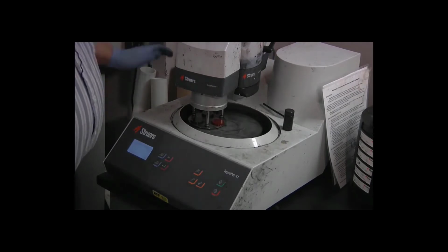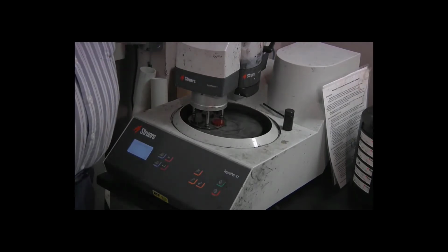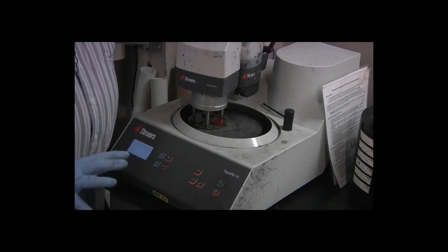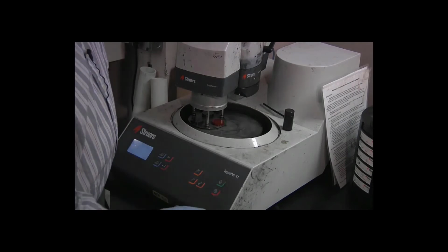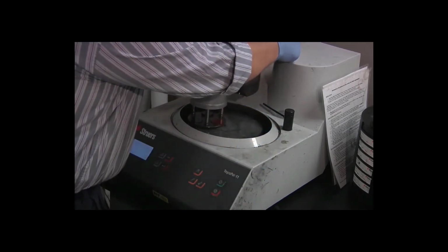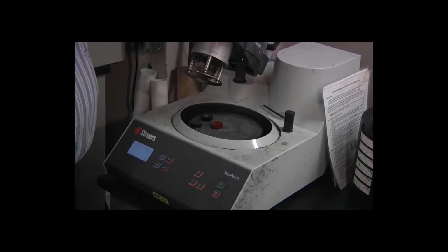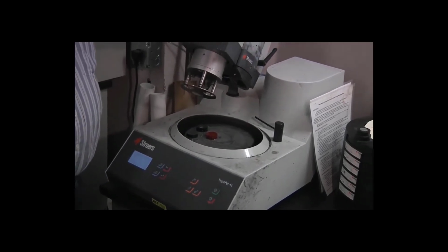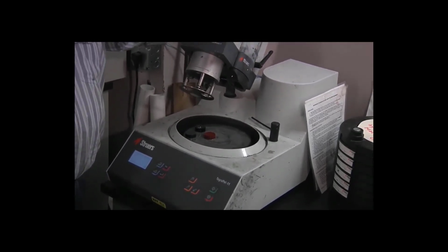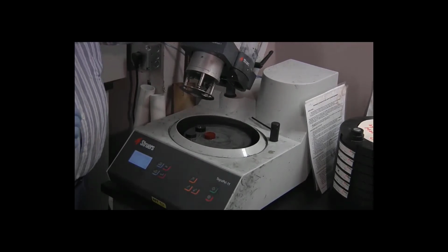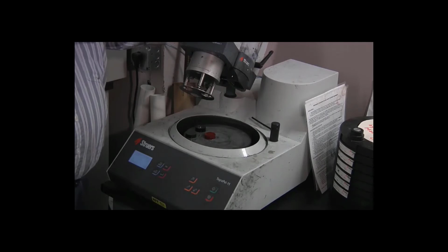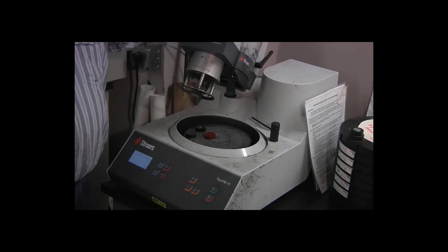Okay, so this stage of the process when we're doing the polishing, we have a different procedure for removing the specimens from the disc. So I'm going to raise the head, and I am not going to take all of the specimens off at once. At this point, we don't want to rinse the surface with just water, because water will leave stains on the metal surface.